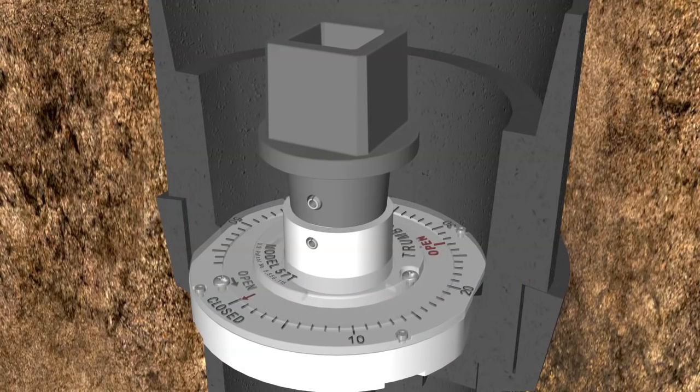Next, ensure that the cast iron housing is properly seated in the valve box. Seat the position indicator in the housing adapter. Make sure the 2 flats on the position indicator are captured between the 2 matching shoulder flats in the housing adapter. This is to prevent the position indicator base from rotating while operating the valve.